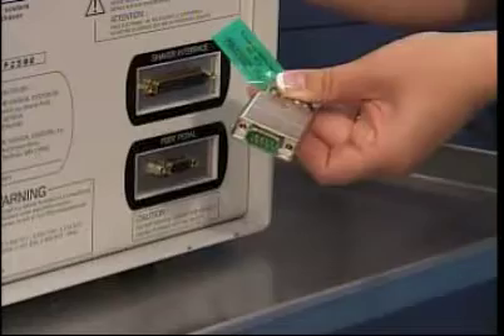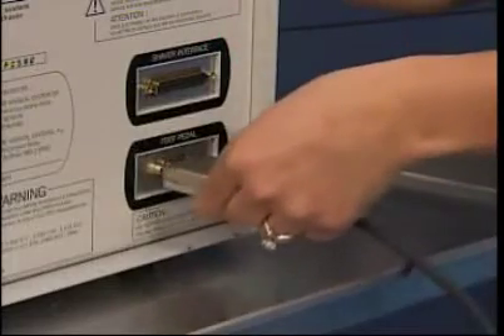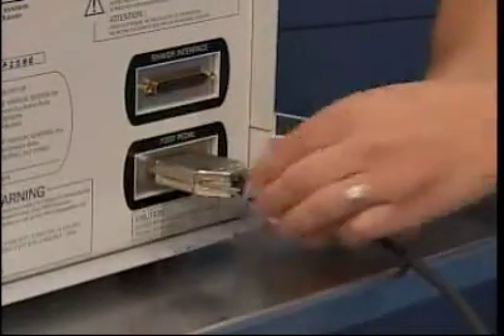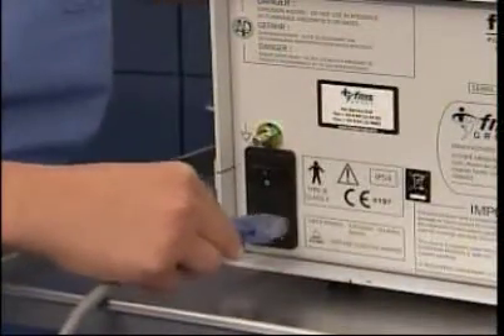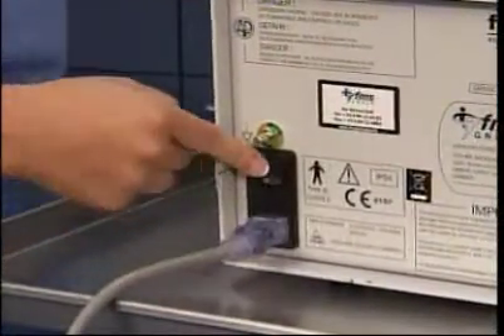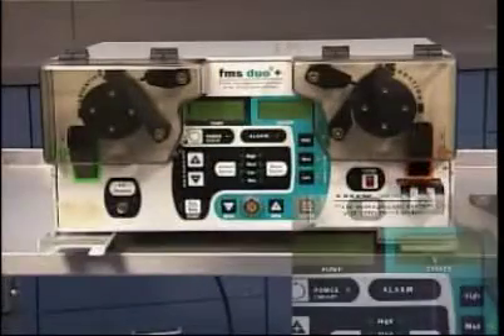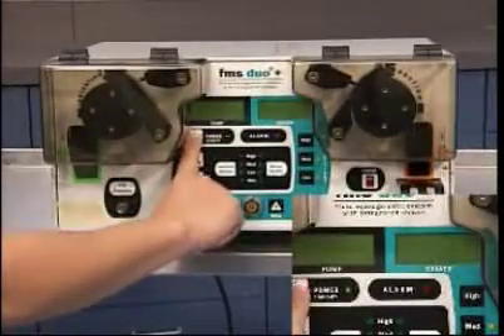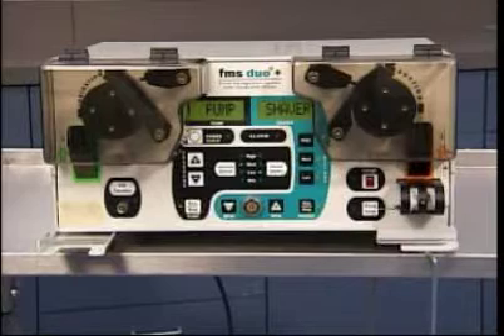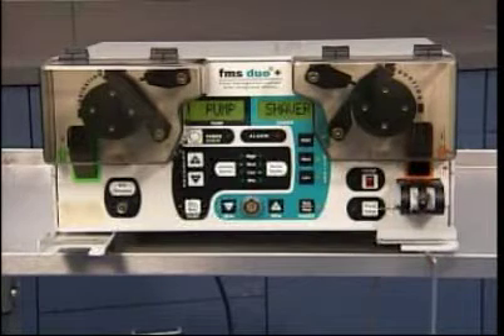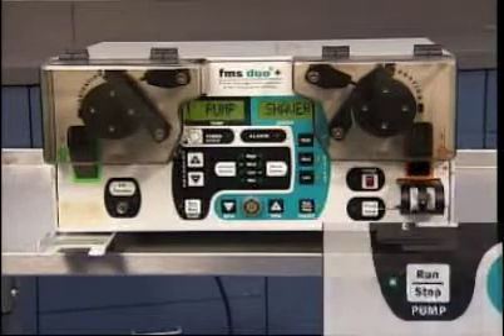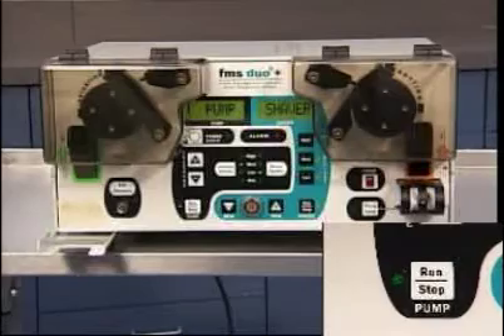Attach the multi-pin connector from the foot pedal to the back of the pump. Attach the power cord to the back of the pump. Turn the main power button on the back of the pump. Then turn the power button standby on the front of the pump. You will hear a short beep. The words pump and shaver will appear in the front screens. You will also see a green LED light blinking next to the run stop button.